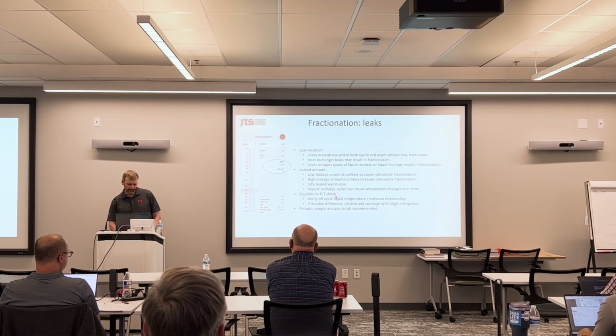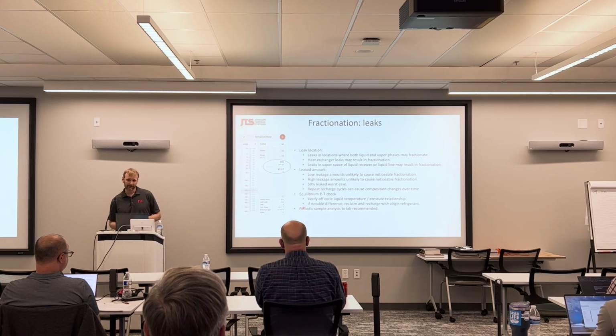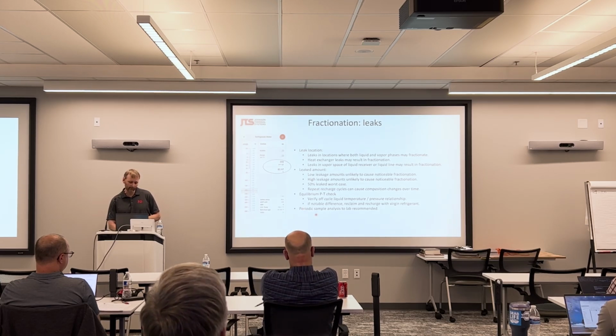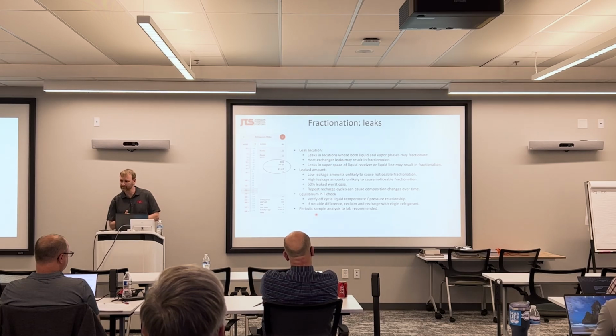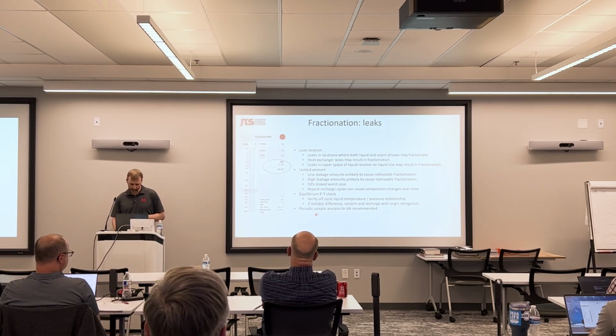One thing you can do is an equilibrium PT check. This requires calibrated sensors. During the off cycle, you can compare your liquid line temperature and pressure to what you actually measure. If the two are substantially different, you might have fractionated refrigerant. It's pretty hard to accurately measure within 5 degrees and even within 5 psi. So generally speaking, I would recommend sending a sample to a lab for component verification of what's in your refrigerant if you happen to have a leak and want to reuse your refrigerant.